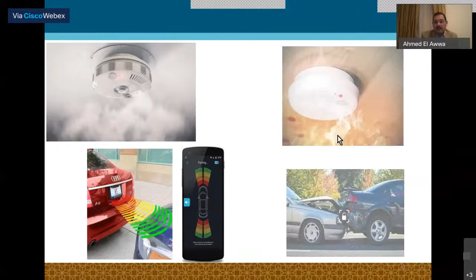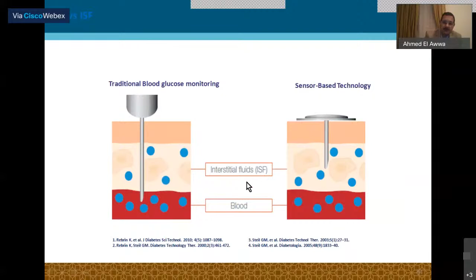The sensors actually do not sense the blood sugar; they sense the subcutaneous interstitial fluid. It's not the blood, unlike the traditional blood check by self-monitoring of blood glucose. It sends data through an electrode and takes data every 5 minutes, or even every 1 minute with the new sensors. It might need calibration: you calibrate the sensor with 2 to 3 blood glucose readings, entering them into the sensor. Or better, with the new sensors, they are factory calibrated.